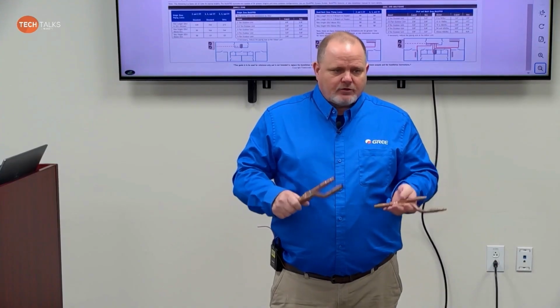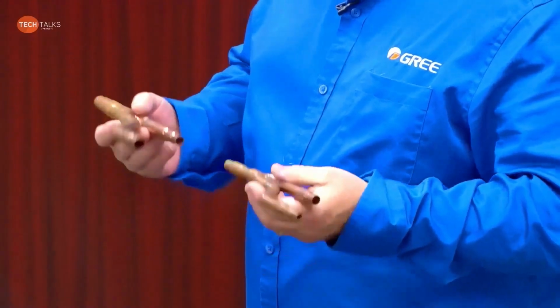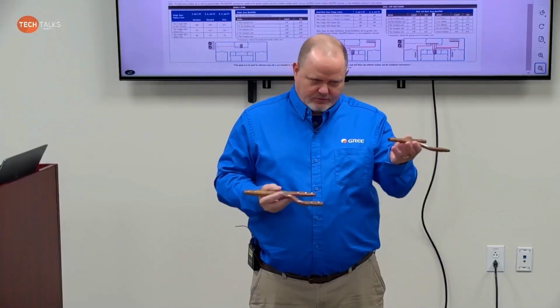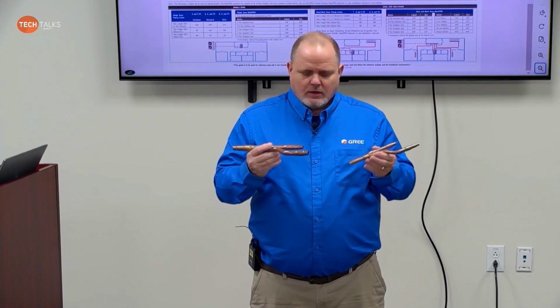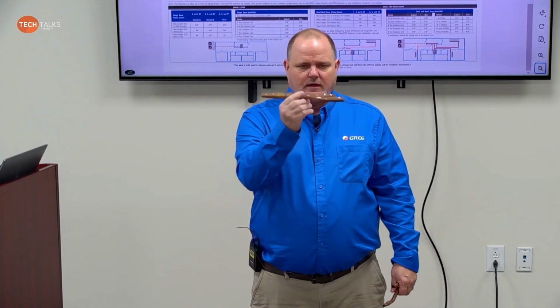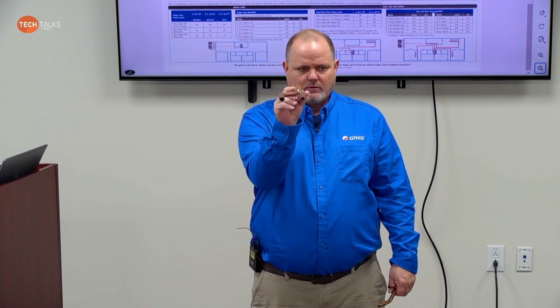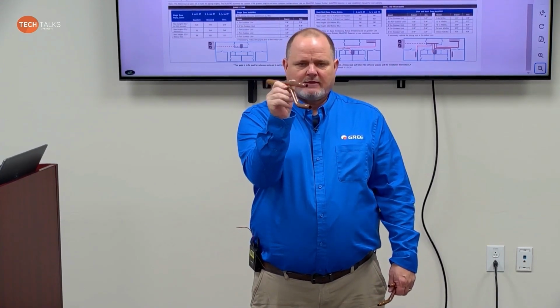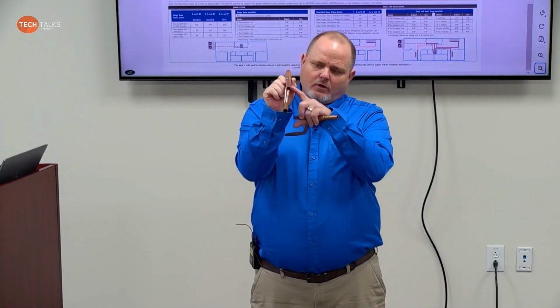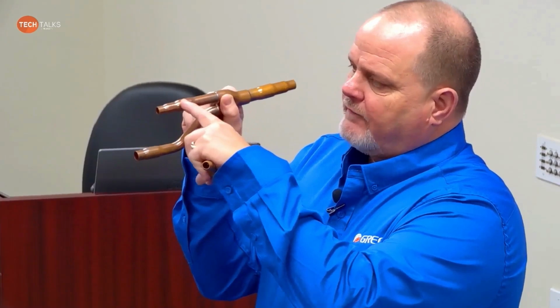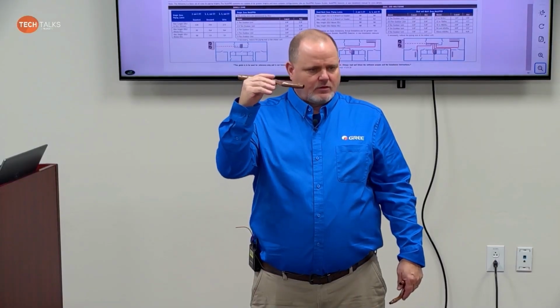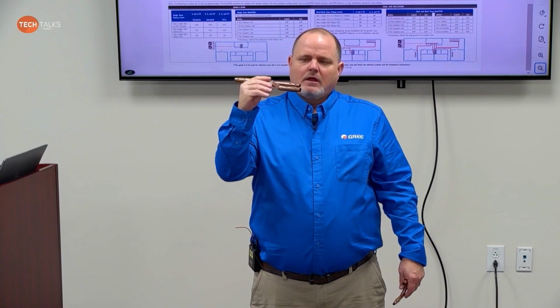The Super Multis and MultiPRO both used Y branches. So the thing with that is, and we ran into it quite often, where these were installed wrong. If they're installed horizontally, they have to be 100% level. They cannot be like this. The problem is all your refrigerant is going to go through that lower pipe and you're going to get very poor refrigerant flow in the upper pipe. So these Y branches can be installed horizontally. They have to be within 15 degrees, and that's what the quick reference guide shows you, but preferably level, okay? And they should be strapped so that they can't come unlevel.